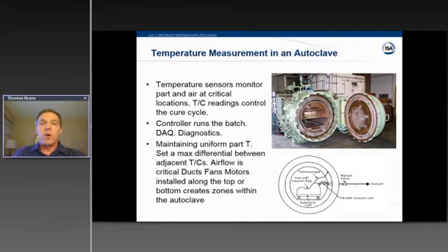Okay, a little bit more. Here's a look at an autoclave. And temperature measurement is obviously very important for this. So temperature sensors are monitoring the temperature of the air around the part, and the temperature of the part itself. And these are what are used in the cure cycle as part of the recipe. So there's a controller that runs the batch, there's a data acquisition system, and there's diagnostics that typically go along with it. Diagnostics to check the health of the sensors to make sure you're getting a good reading.